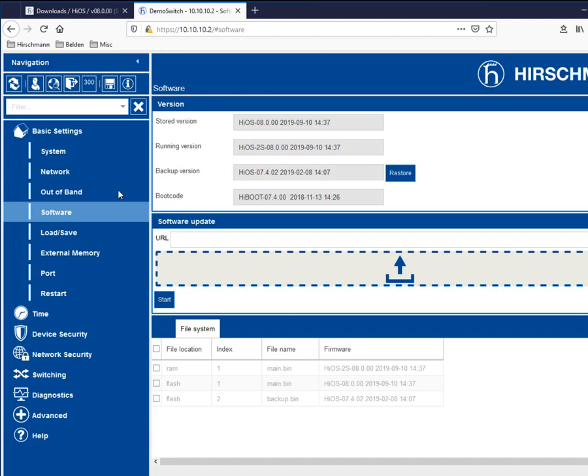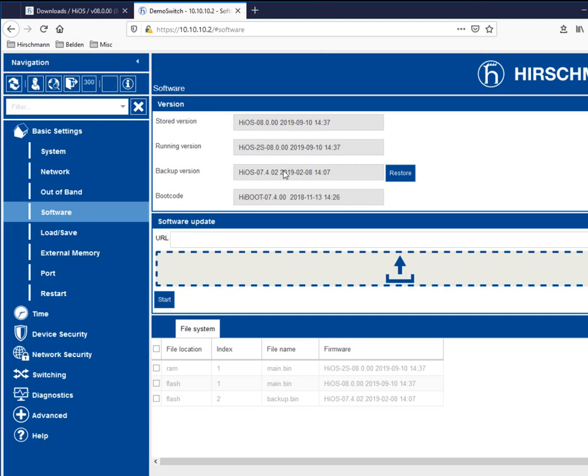And you will now note that not only is the stored version 8.0, but the running version as well. The older version that was in here is now the backup version. And what this allows you to do is if you ever need to revert, you simply click on the restore and you will then revert back to the older firmware rev.